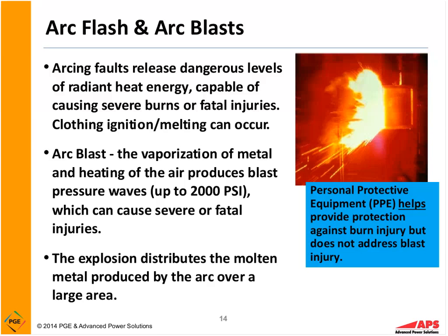They actually have to take a layer of skin off with that. So we have the arc blast. The vaporization of metal and the heating of air produces blast pressure waves up to 2,000 PSI, so that's pounds per square inch. So if we have a larger arc flash event, we can actually receive internal injuries from the blast pressure wave. In other words, the blast pressure wave may blow us back, we may fall on something, we may fall off a ladder, or we could also just receive internal injuries and, in some cases, death. So we could see a fatality.